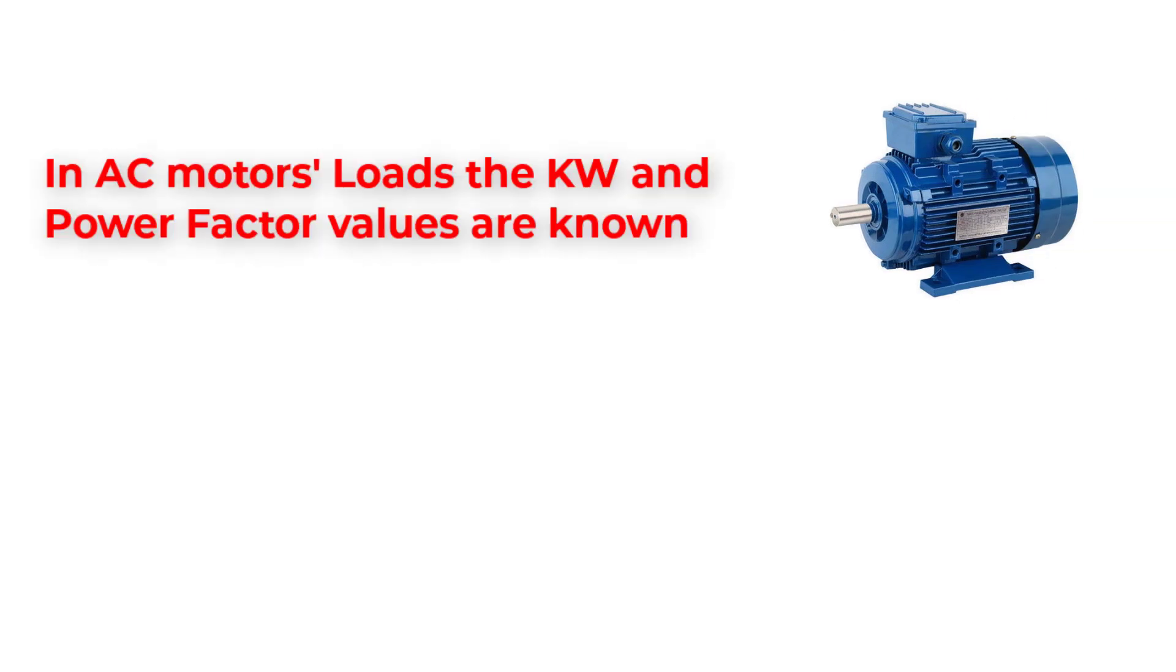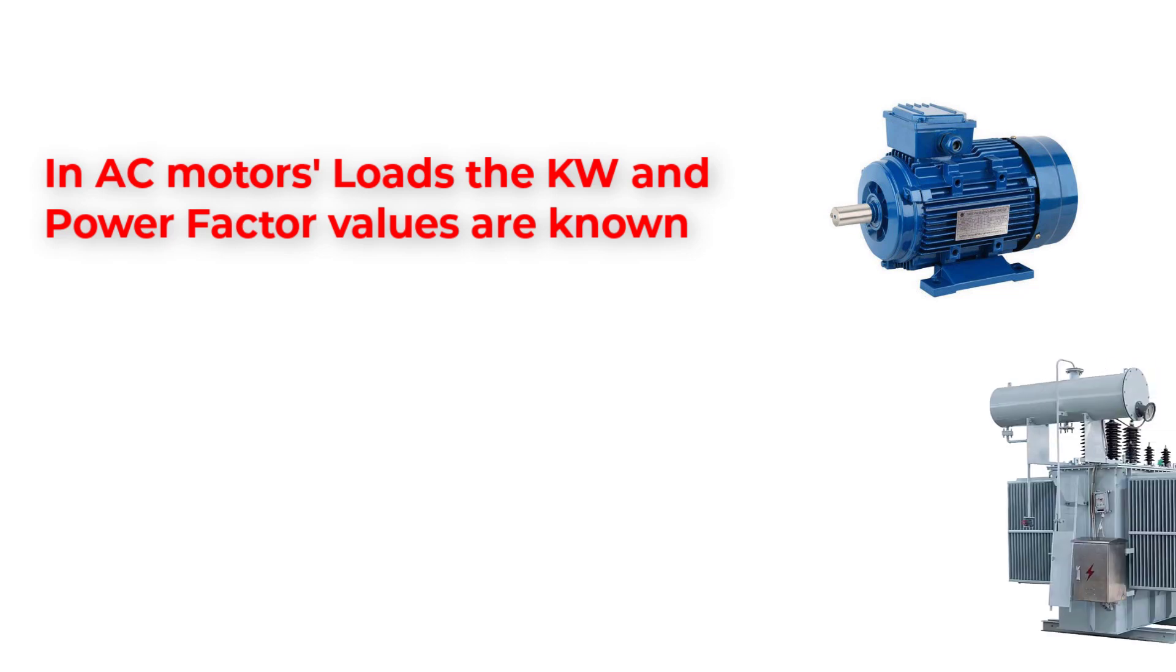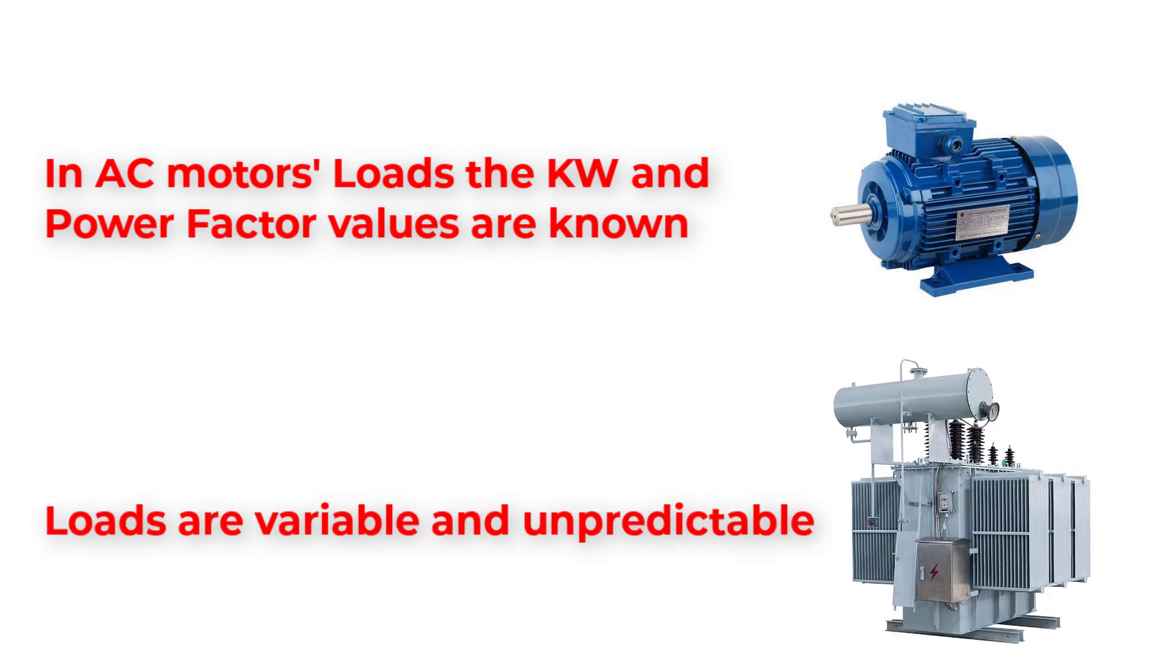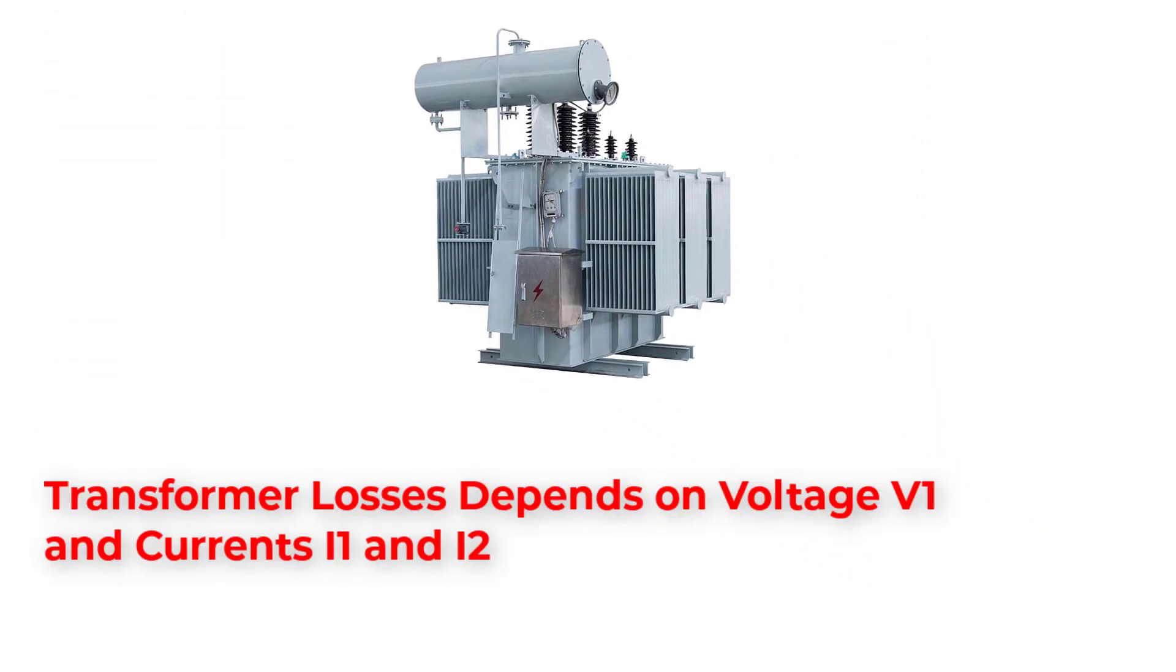Let's make a recap here. AC motors are loads that we know its power factor, so we can express its rated power in kilowatt. But for transformers, we cannot expect the power factor of the load. So, we deal with the total power kilovolt ampere. And also, the losses of transformer depends on the volt times amps.